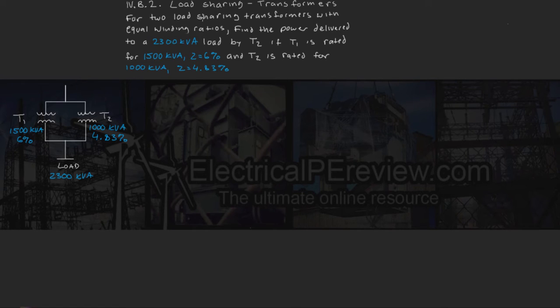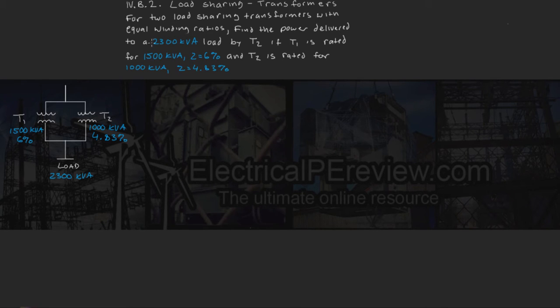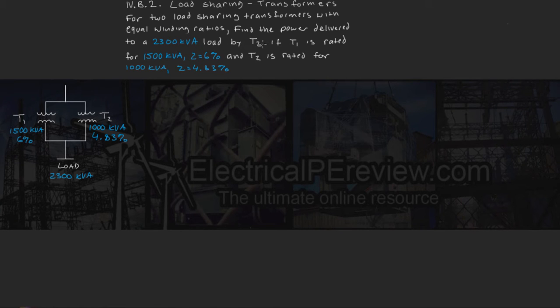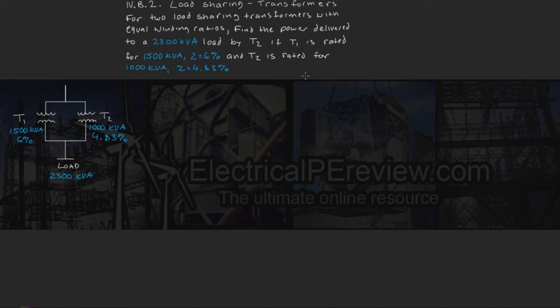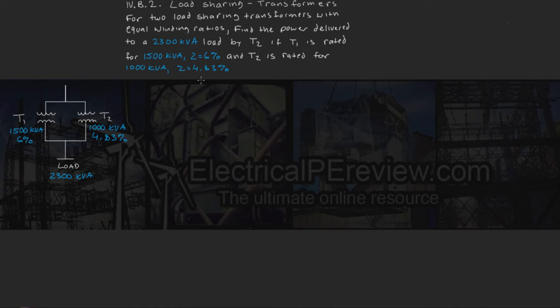For two load-sharing transformers with equal winding ratios, find the power delivered to a 2300 kVA load by transformer 2 if transformer 1 is rated for 1500 kVA with a 6% impedance and transformer 2 is rated for 1000 kVA with a 4.83% impedance.